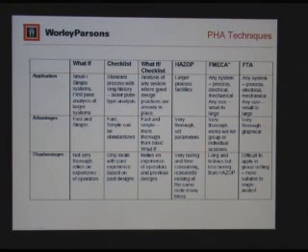And you can see the what-if is used for simple and small systems. And it's best used for the first pass analysis of larger systems, followed by some detailed analysis. And it is fast and simple. The disadvantage is it's not very thorough, and it relies on the experience of the operators or the people who are conducting the study.